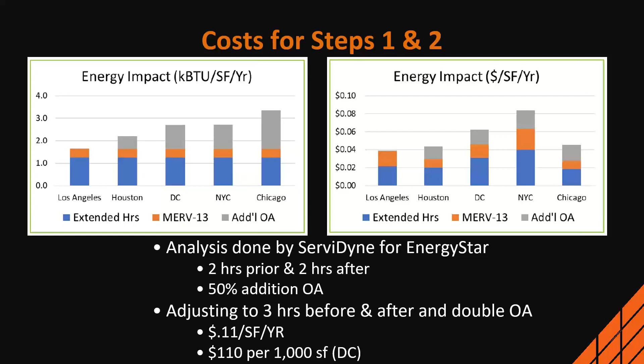For what they did in their study, which was 2 hours prior and 2 hours after for the extended period of time, and 50% additional outdoor air because you had to pick a number, it's roughly 6 cents a square foot per year. So if we adjust that to the 3-hour recommendation we were making, and doubling per our example case, it gets to 11 cents a square foot per year. Again, it's not a huge number, it's basically $110 per 1,000 square feet. So there's a little bit of money there, but again, it's not a permanent item. It's a pandemic response, so it's very doable.